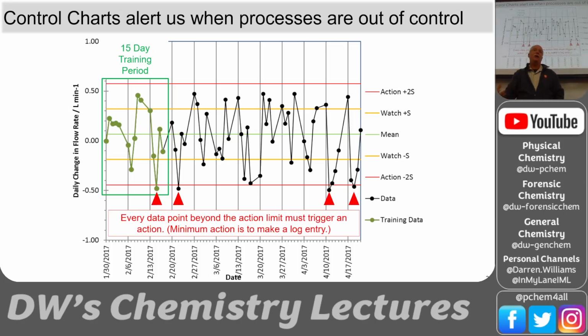Now, if this was a gas chromatograph and our retention time was bouncing around randomly, but then one day it was really short, that means it came out fast. So what is our action? Well, our action is to explore: did the flow rate change? Maybe the flow rate was faster, and so it came out in a shorter retention time. Maybe the temperature control was off, and it was hotter, so it came out faster. There are a lot of things that can affect that, but we would take the action by exploring our equipment or our process.